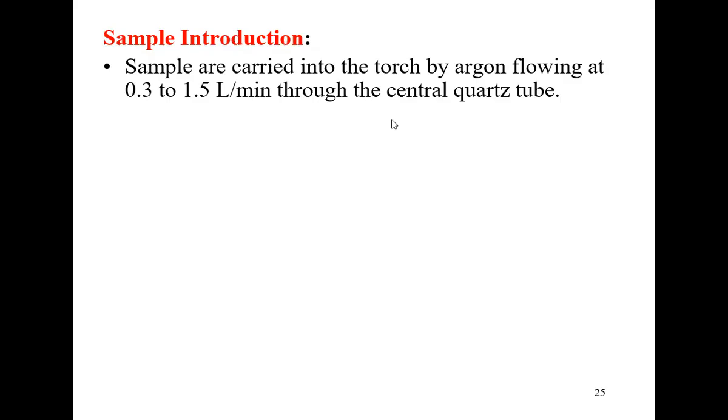This is not a liter. I'm holding something here, almost. If I fill it, we are consuming that much per minute, right? So that's a lot. If you think of the tank, you are consuming a lot of it, actually. So this is 0.3 to 1.5 liters per minute through the central quartz tube.